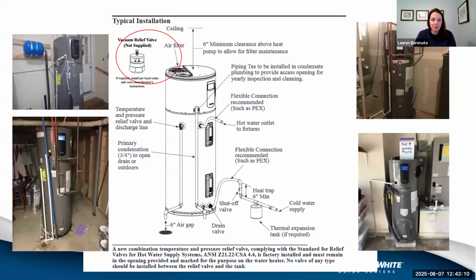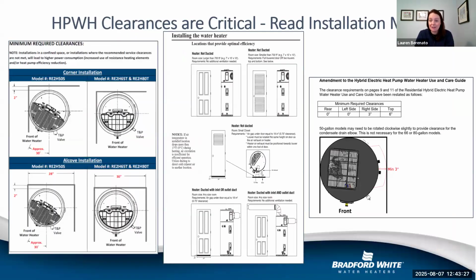A couple examples of typical installations that we'll see for heat pump water heaters. Again, this is from 2 years ago, so heat pumps were becoming prevalent, but are definitely more prevalent in the market now. This shows the airspace requirement for typical installations. You can see garages, what looks like an attic, and a basement. As I mentioned, make sure you're reading the installation manual. I cannot emphasize this enough. This is what will make it successful. You can see here it's modeling the differences between a louvered door versus a non-louvered door, and letting you know the varying aspects of install.